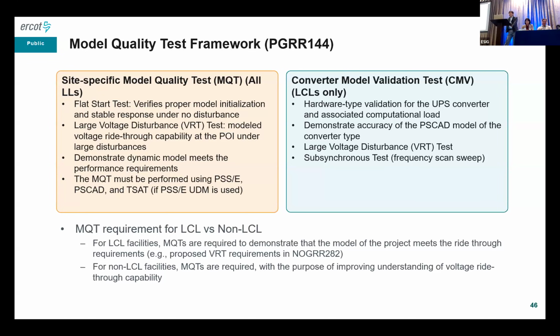It has a site-specific MQT and also a converter model validation test. Site-specific MQT consists of a flat start test and a large voltage disturbance test. You should not move if there are no system disturbances; it should be flat. And for the large voltage disturbance test, they can test the voltage ride-through test curve to demonstrate they meet the performance requirements. Again, the MQT must be performed using all three software.